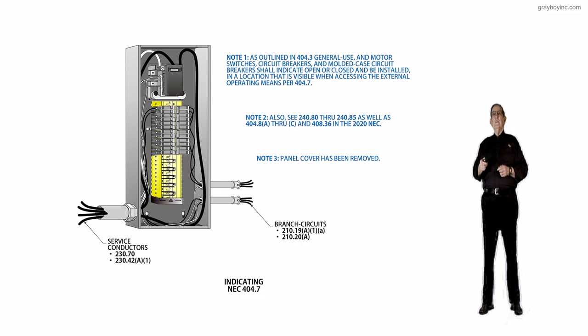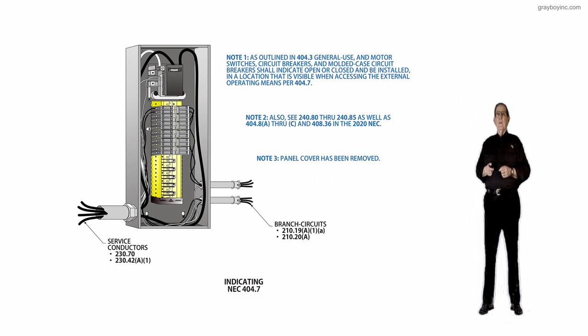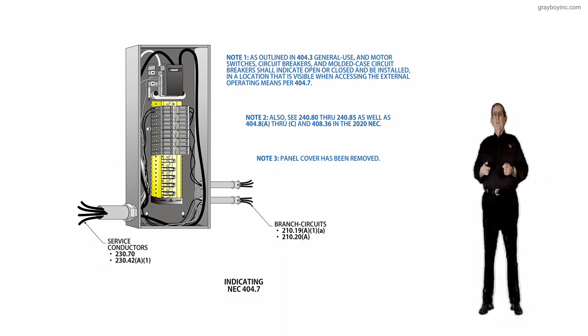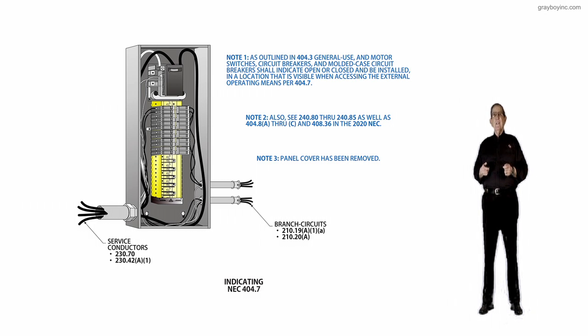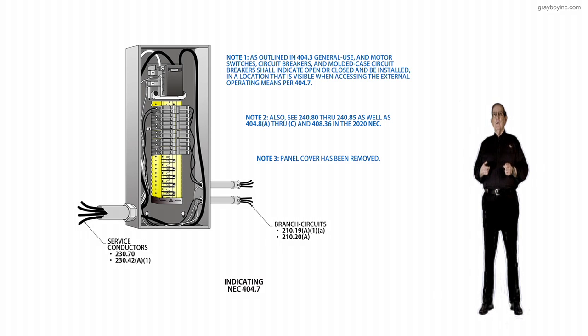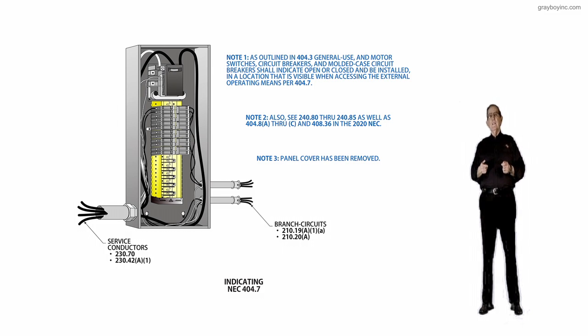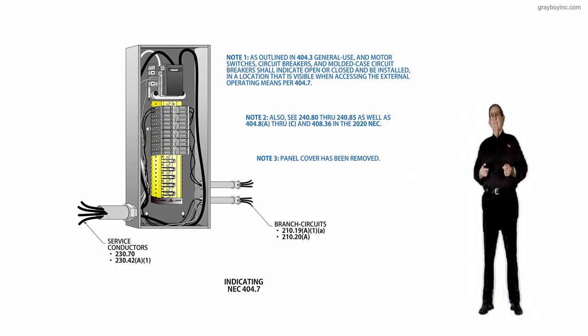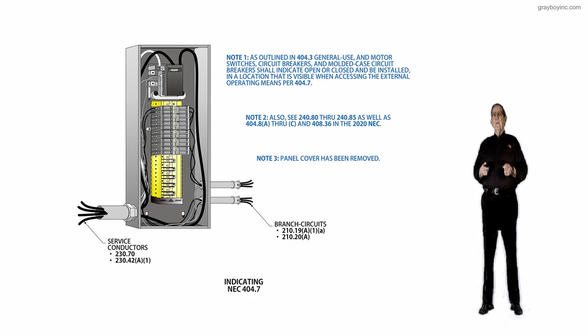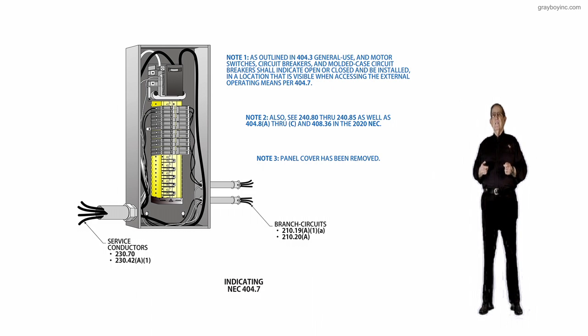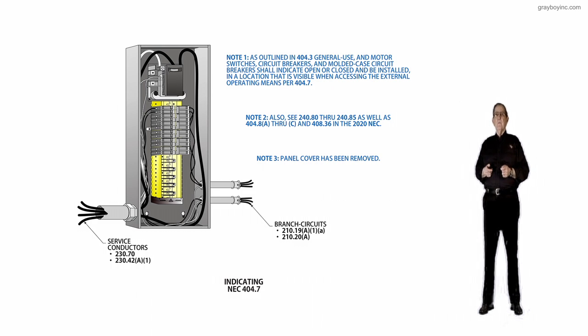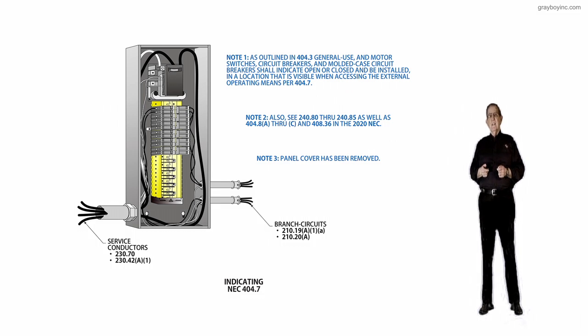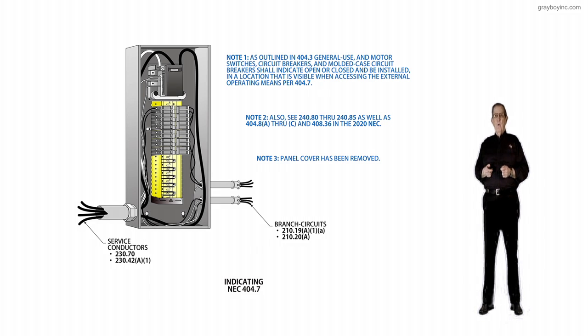Note 1 at the very top is outlined in 404.3. General Use and Motor Switches, Circuit Breakers, Molded Case Circuit Breakers shall indicate the open or closed position and shall be installed in a location that is visible when accessing its external operating means, as outlined in 404.7.